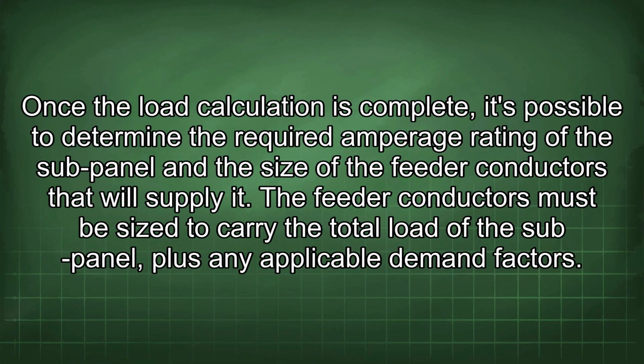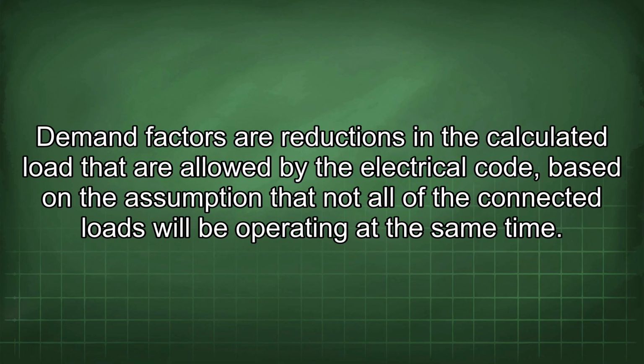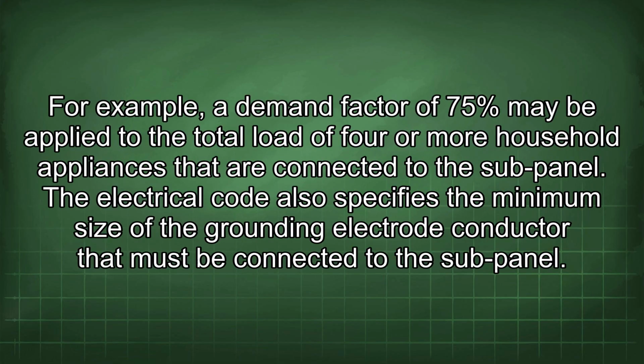Once the load calculation is complete, it's possible to determine the required amperage rating of the sub-panel and the size of the feeder conductors that will supply it. The feeder conductors must be sized to carry the total load of the sub-panel, plus any applicable demand factors. Demand factors are reductions in the calculated load that are allowed by the electrical code based on the assumption that not all of the connected loads will be operating at the same time. For example, a demand factor of 75% may be applied to the total load of 4 or more household appliances that are connected to the sub-panel.